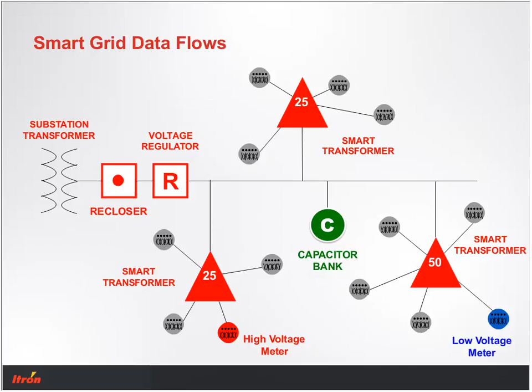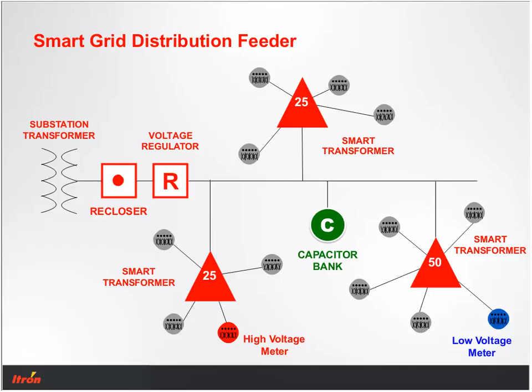This is the typical configuration of one of our feeders. You can see the recloser and the regulator in the station, with cap banks out on the line. What you don't see is the smart switch that would be at the end of this, connecting to the next feeder downstream. Then we've got the smart meters tied to the smart transformers. What we're interested in here, since we're looking at voltage optimization, is the high voltage meters and the low voltage meters, coded in red and blue. We'll be leveraging those devices to understand how to make the most of this voltage optimization scenario.